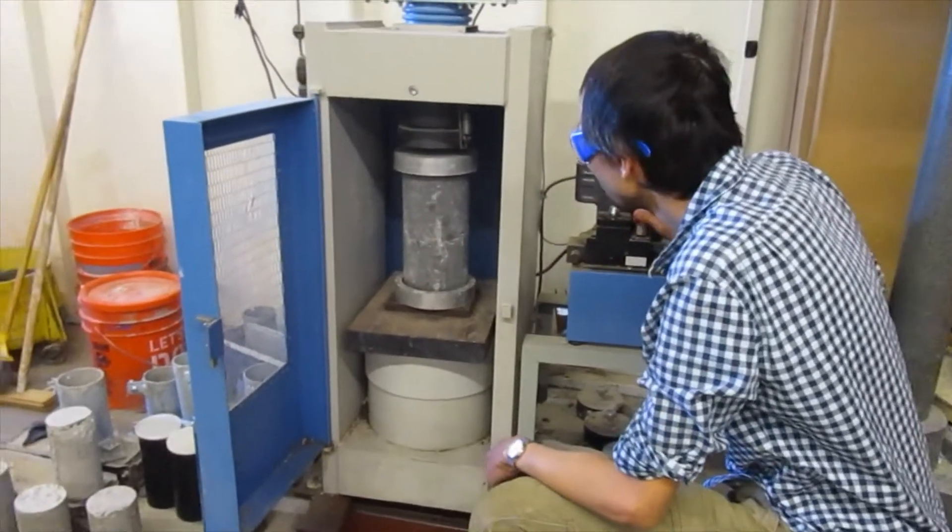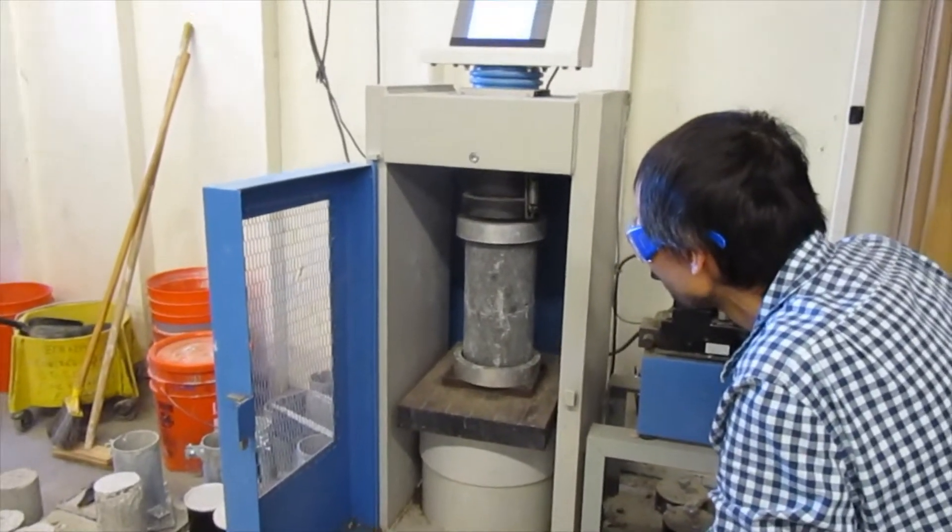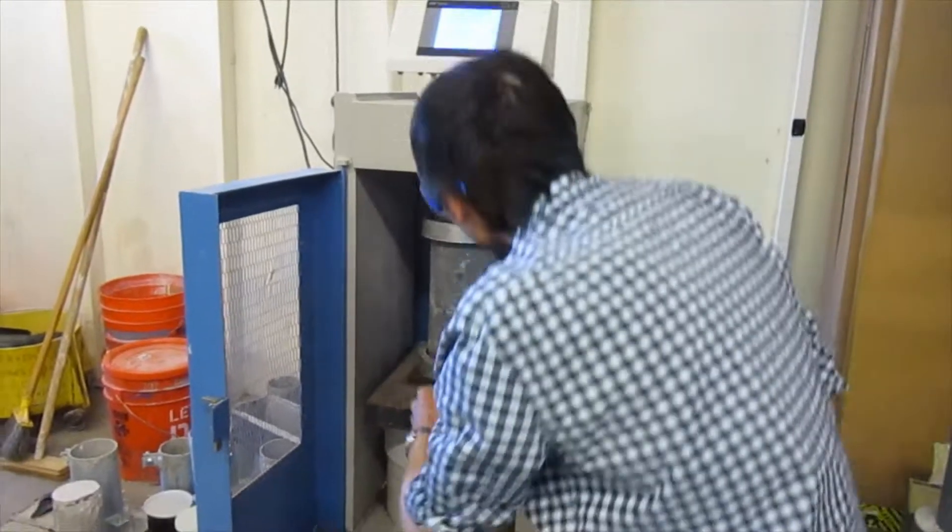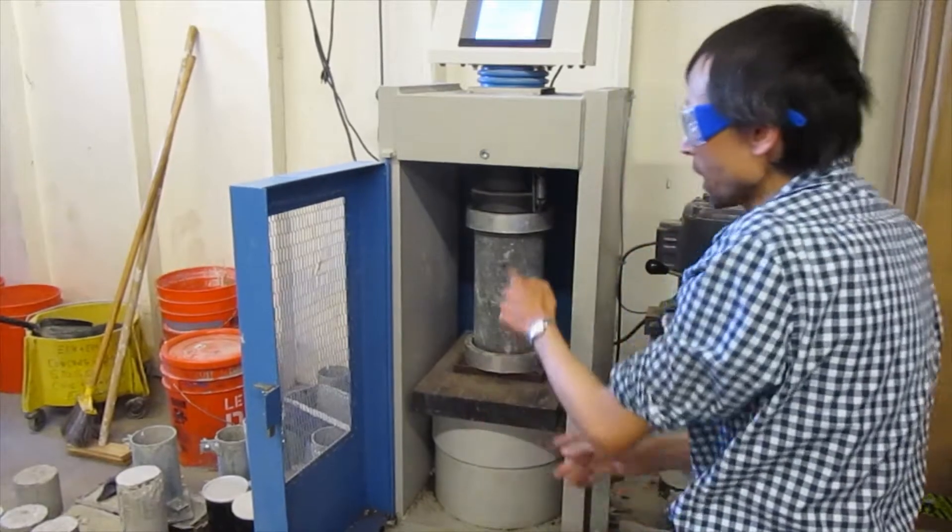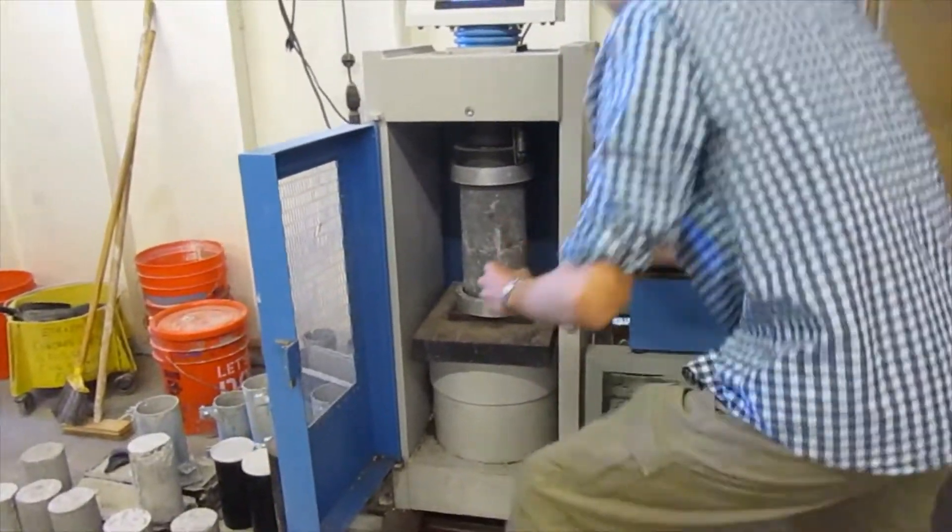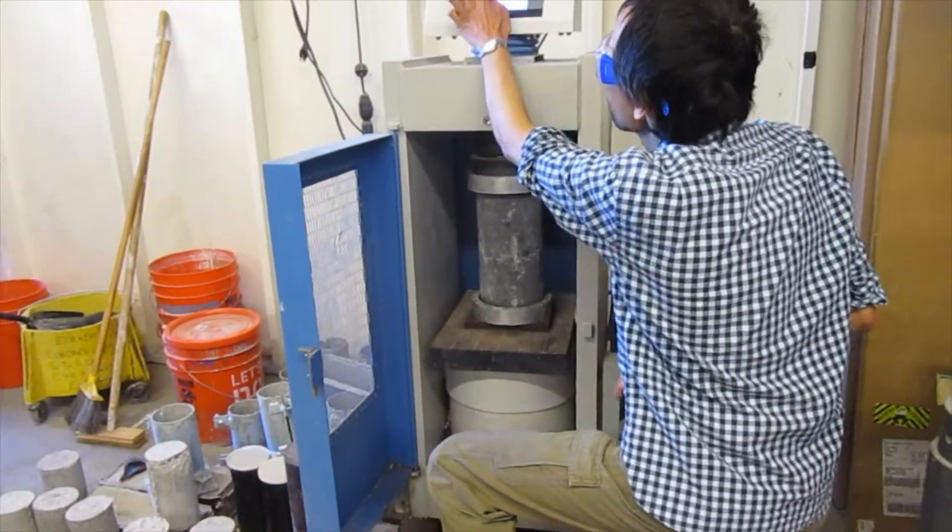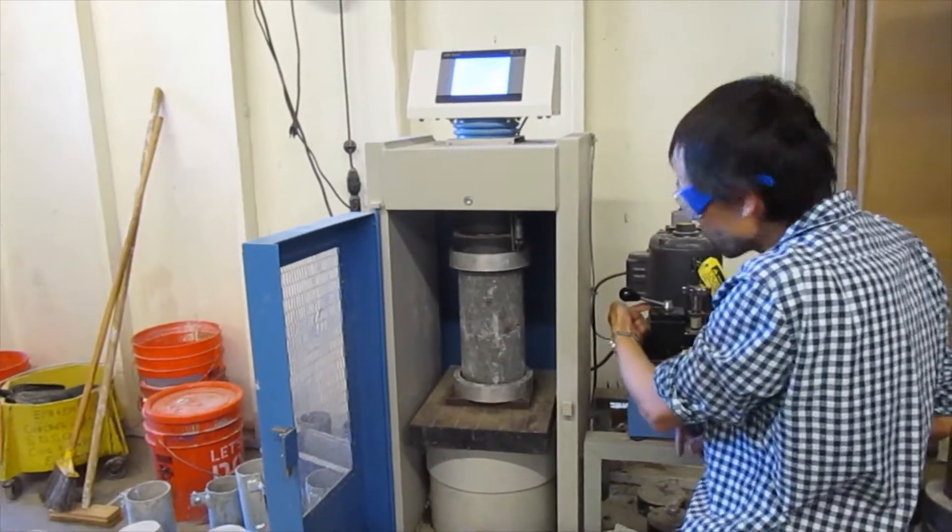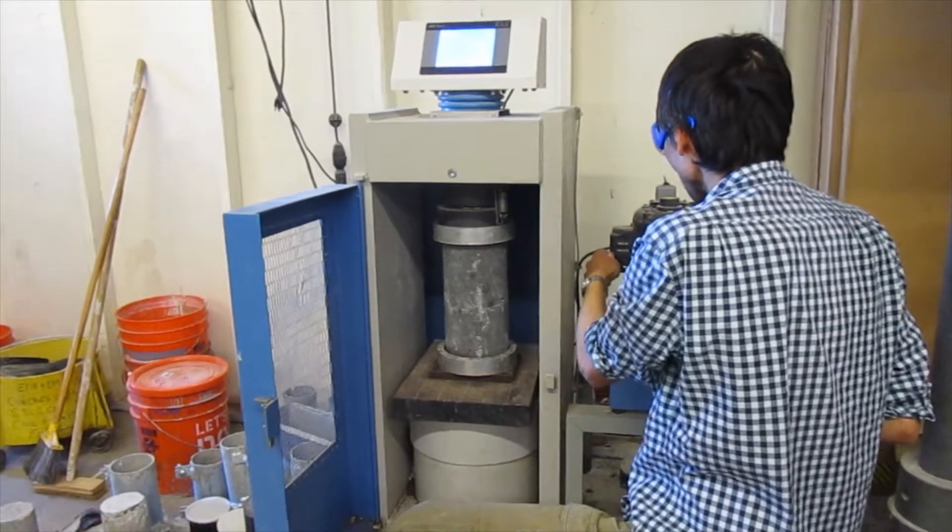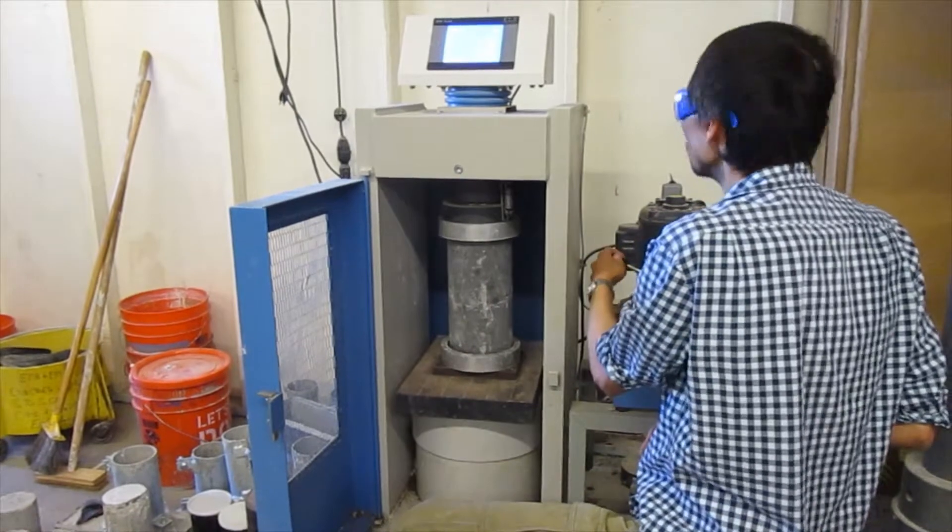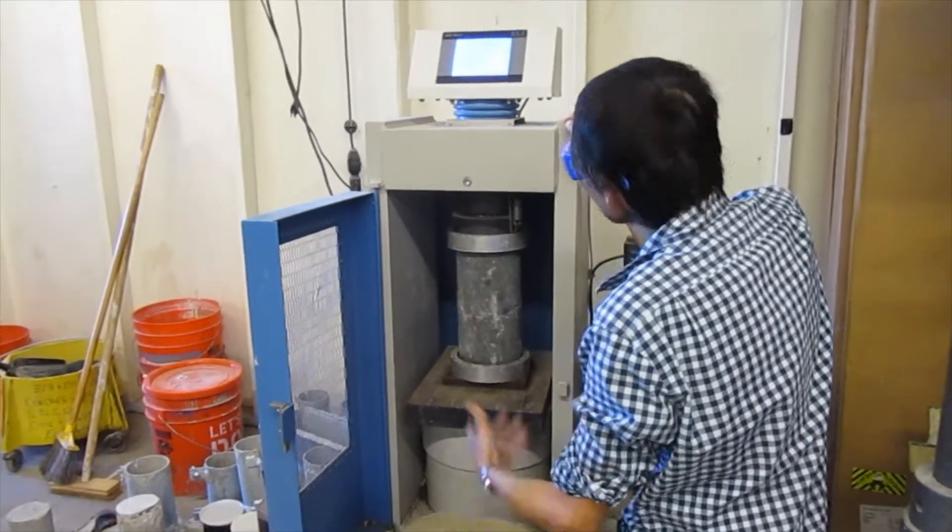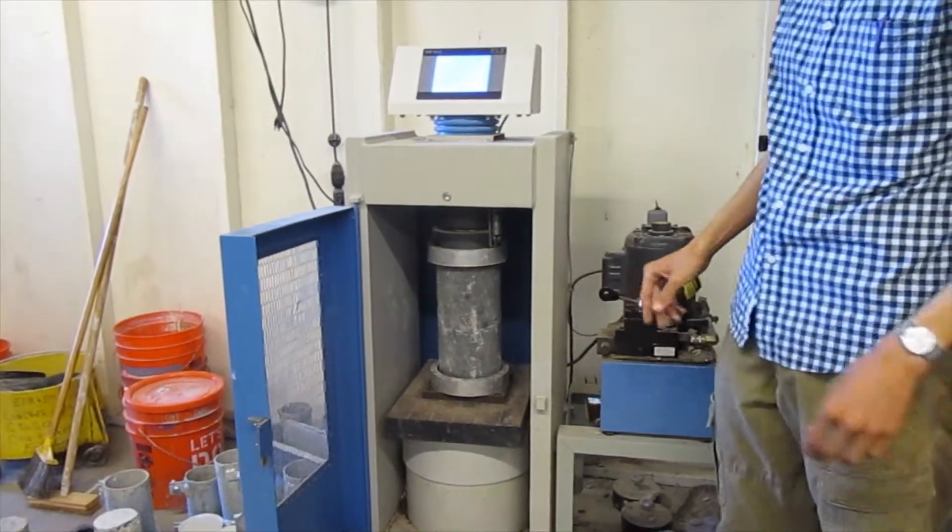See the bottom ram coming up? Now I'm going to rotate it to hold. I'm on hold right now. I'm going to center that on the top of the specimen. Full advance. Hold. About a 380 pound preload. So I want to back off a little bit. So I'll switch it to retract so I can back off the load a little bit. But I have to be kind of quick because I don't want it to retract too much. I can go with that. So right now I'm on hold. I think I'm ready to start this.